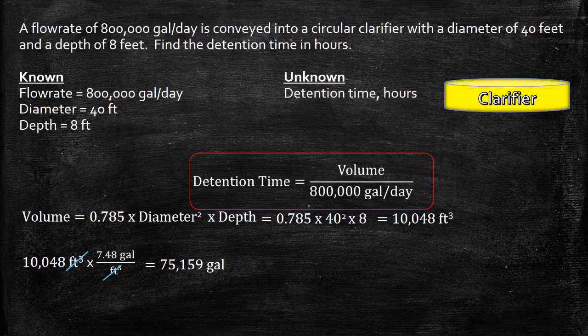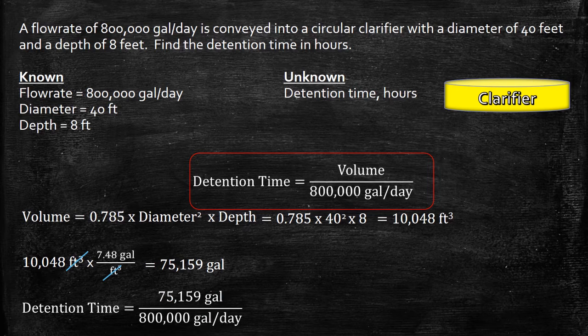Now we can take this volume and plug it back into the detention time formula. Detention time equals 75,159 gallons divided by the flow rate of 800,000 gallons per day. The gallons cancel out.